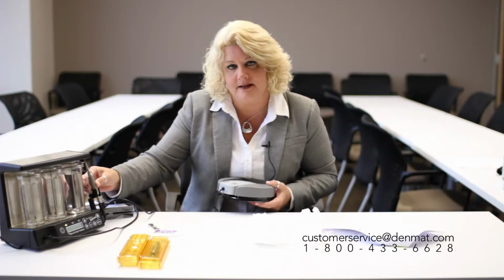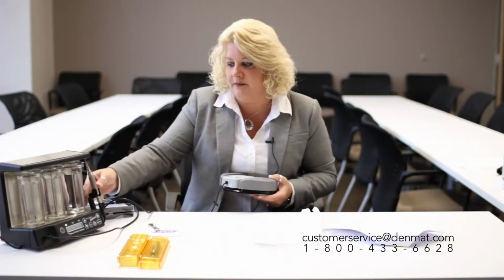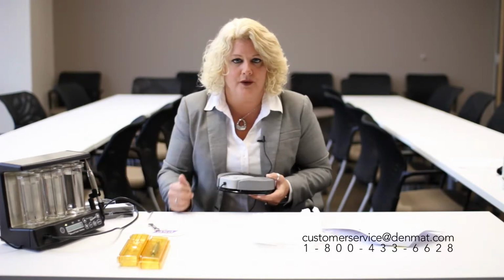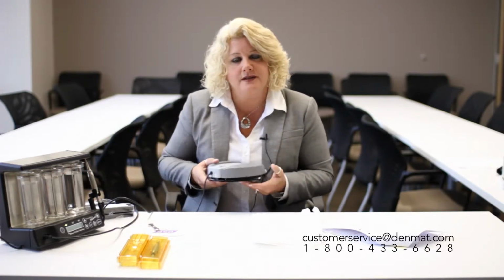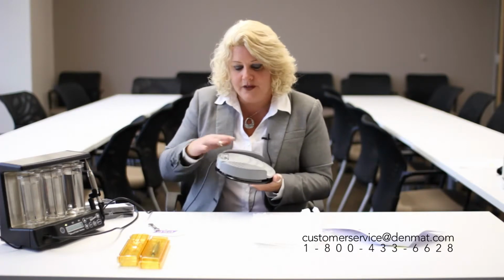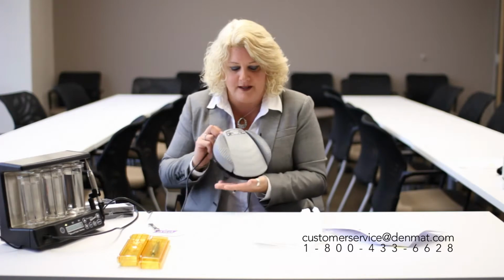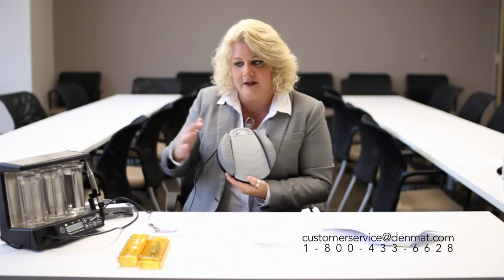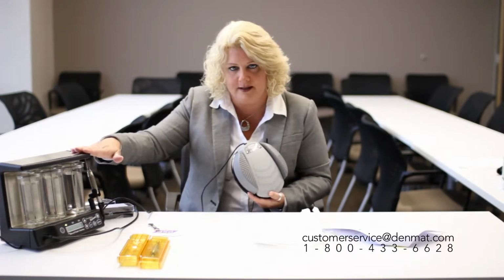If you have other units in the office, what we would request is that you go to those units and find out if there is a handpiece that's not working. Is that the only handpiece that's not working, or is it all of the handpieces that you have in the office? You will have multiple handpieces that you've bought with your unit, and we'll ask you to do the same thing with the foot pedal as well. So if this foot pedal for this unit isn't working, they are interchangeable. If you have other foot pedals that look like this in the office, swap them out to see if it's this specific foot pedal or if it's the unit itself.